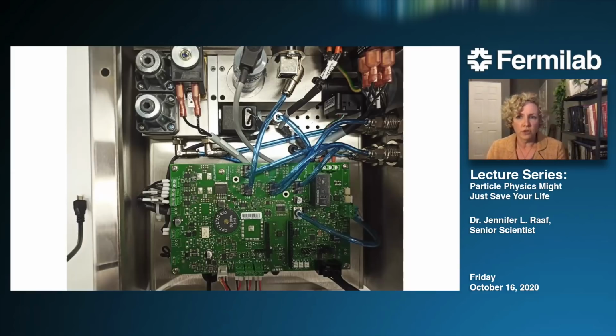This electronics board that you're seeing at the bottom of the image is what has all the pressure sensors mounted on it. And that's what the clear blue tubing is attached to. It also has things like an alarm loudspeaker and the connections for powering LEDs for alarms. And it powers the brains of the device, which are made up of a Raspberry Pi microcomputer and an Arduino.